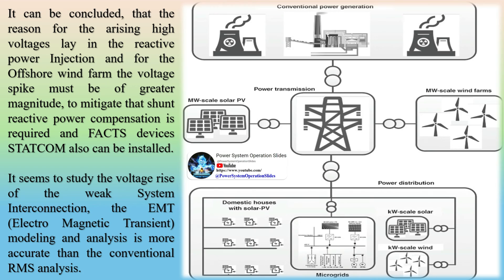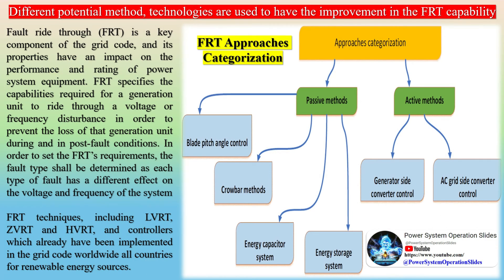Fault Ride-Through (FRT) is a key component of the grid code, and its properties have an impact on the performance and rating of power system equipment. FRT specifies the capabilities required for a generation unit to ride through a voltage or frequency disturbance in order to prevent the loss of that generation unit during and in post-fault conditions. In order to set FRT requirements, the fault type must be determined, as each type has a different effect on the system's voltage and frequency. FRT techniques — including LVRT, ZVRT, and HVRT — and their controllers have been implemented in grid codes worldwide for renewable energy sources.